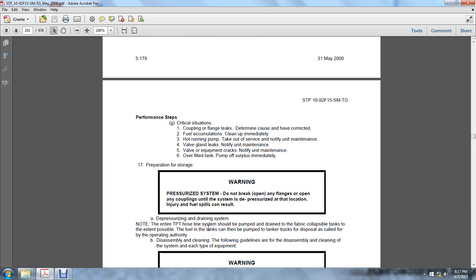17. Preparation for storage. Pressurized system. Do not break open any of the flanges or couplings until the system is depressurized, or injury or fuel spill can result. Depressurizing and draining the system. The entire tactical petroleum terminal hose line should be pumped and drained, and the fabric collapsible tanks emptied to the extent possible. The fuel in the tanks can be pumped into tanker trucks for disposal as called for by the operating authority.